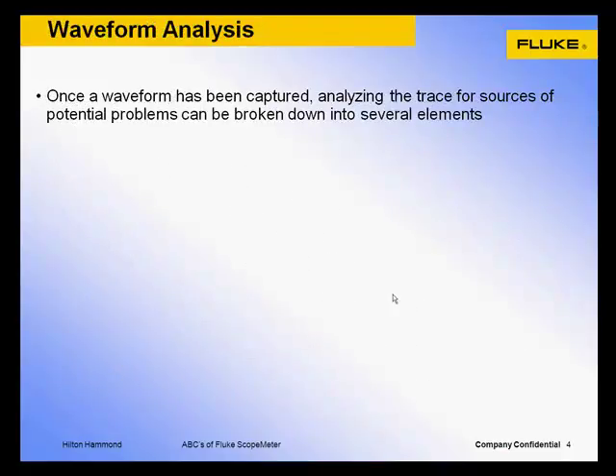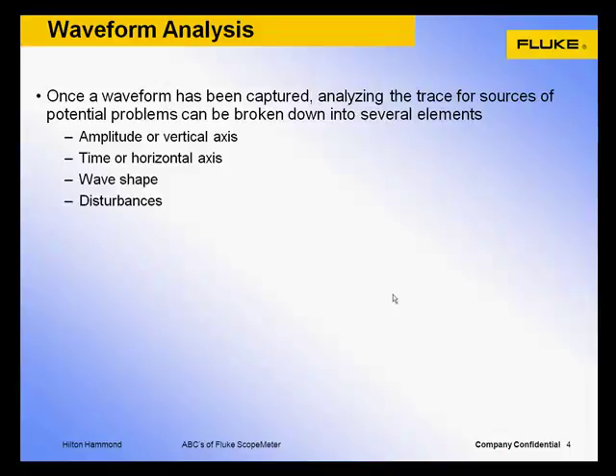To become proficient in analyzing waveform traces, we must train our eye to always look in these four domains. First, amplitude or along the vertical axis. Second, time or along the horizontal axis. Third, look for waveform shape issues. And fourth, look for any signs of disturbances that may be influencing the signal. Train the eye to scan up and down the vertical amplitude, then horizontally back and forth across the waveform time span, then look for waveform shape patterns, and lastly keep a lookout for any external disturbances.